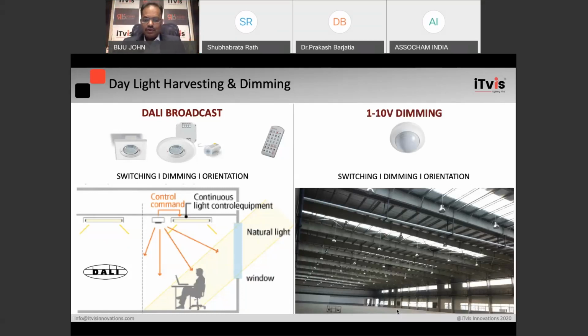To automate this type of industry, what you should do is take a dimming high bay. For example, let's assume you already have an LED high bay which is non-dimming. You need to switch it on and switch it off. What you can do is go for a retrofit option. Take out the driver of this high bay and use an analog dimmable driver. There are a lot of analog dimmable drivers available which don't cost much. 1 to 10 volt dimming.